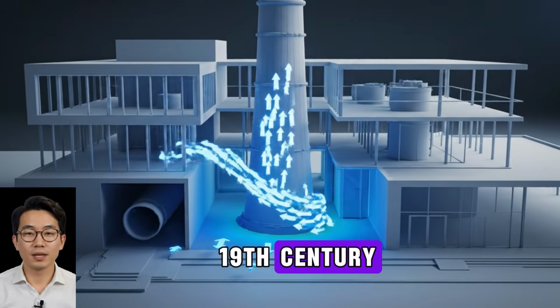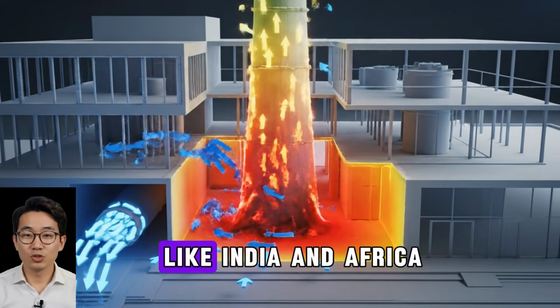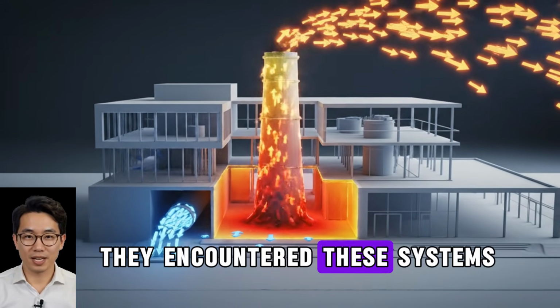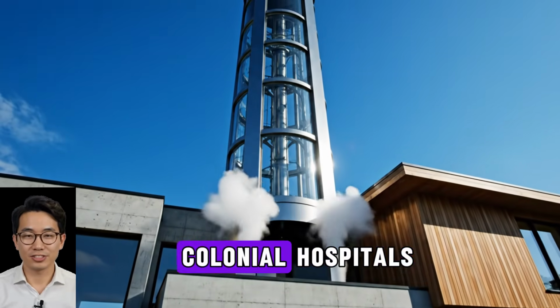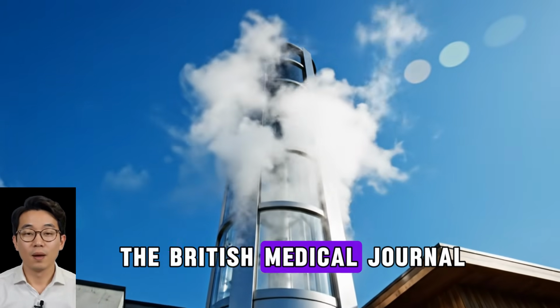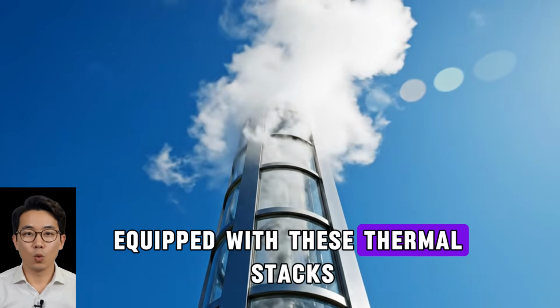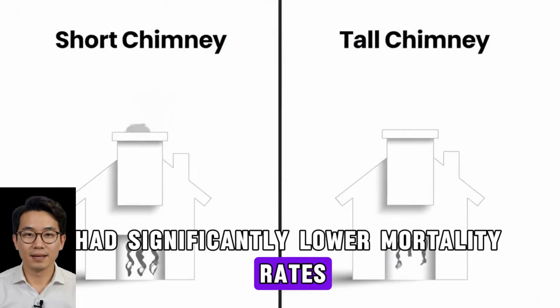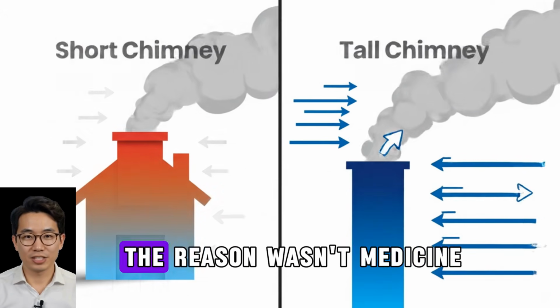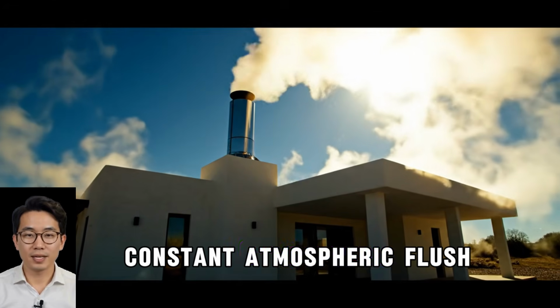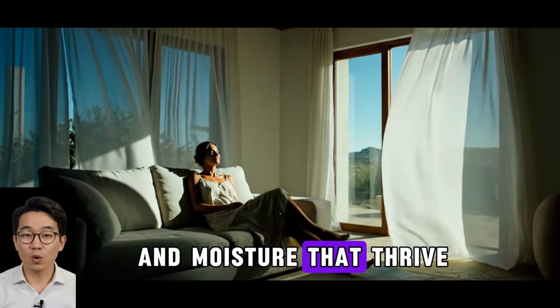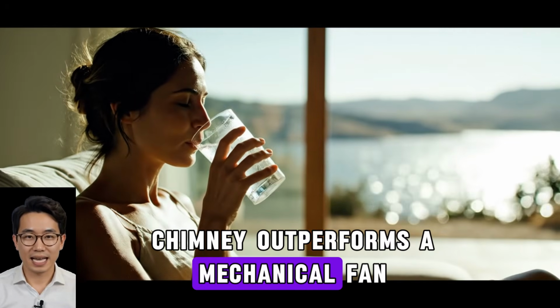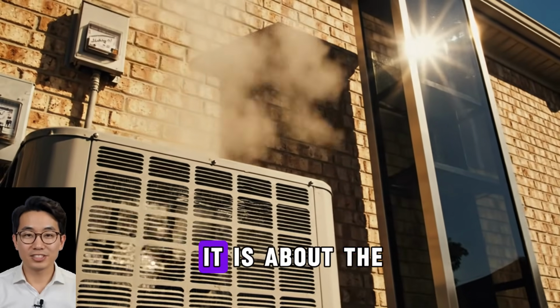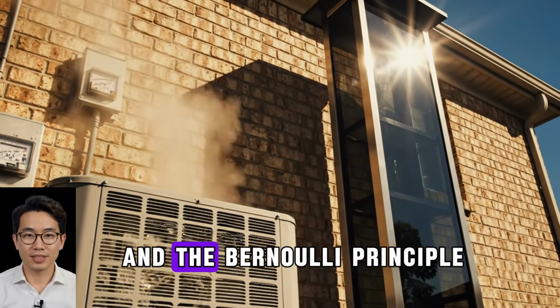By the 19th century, as the British Empire expanded into regions like India and Africa, they encountered these systems and integrated them into colonial hospitals and barracks. The British Medical Journal documented that wards equipped with these thermal stacks had significantly lower mortality rates during cholera and influenza outbreaks. The reason wasn't medicine, it was physics. The stacks provided a constant atmospheric flush, removing pathogens and moisture that thrive in stagnant air. The reason a solar chimney outperforms a mechanical fan is not about horsepower. It is about the physics of the stack effect and the Bernoulli principle.